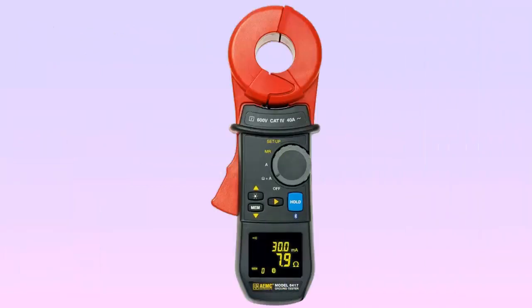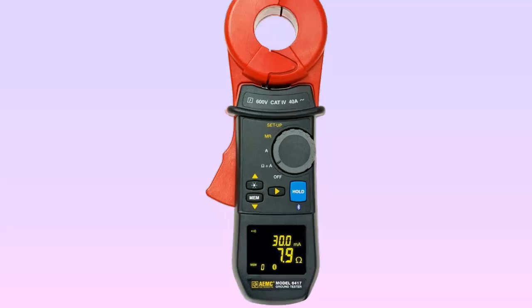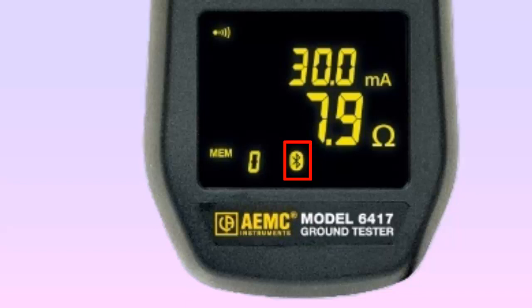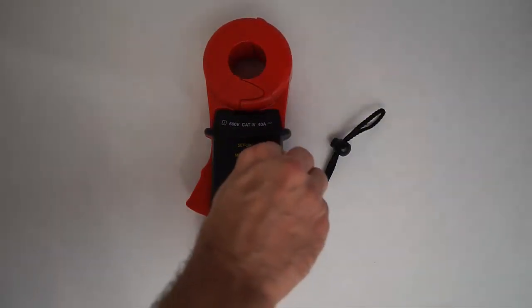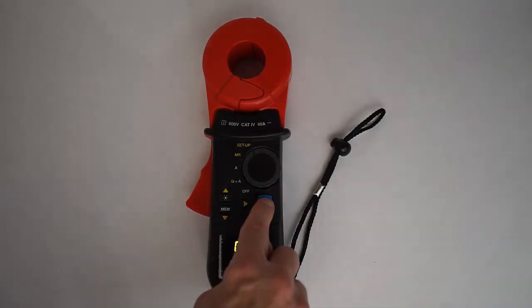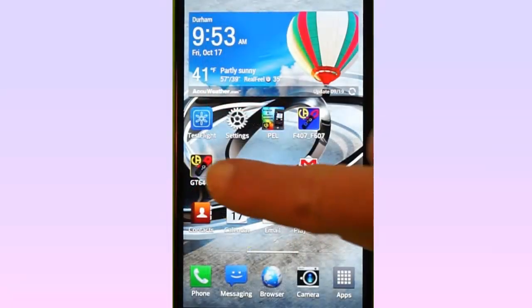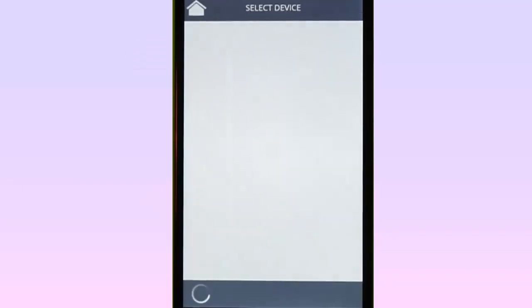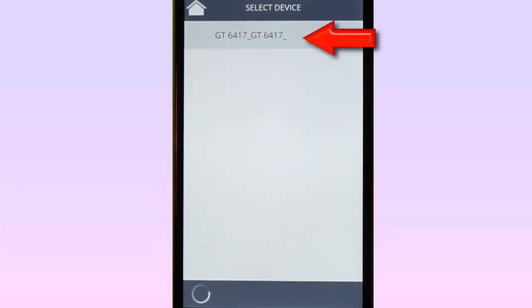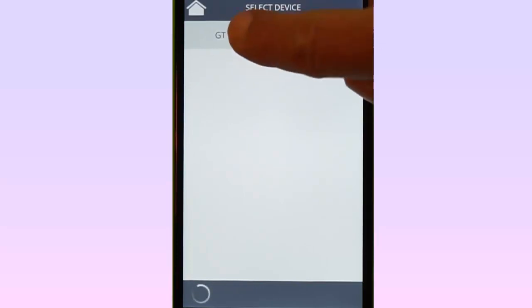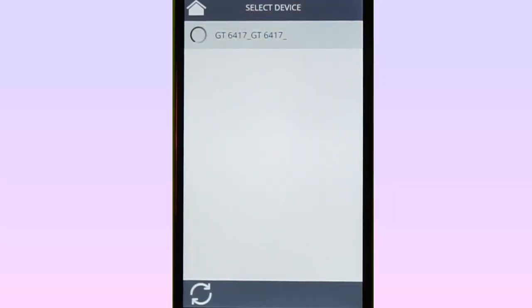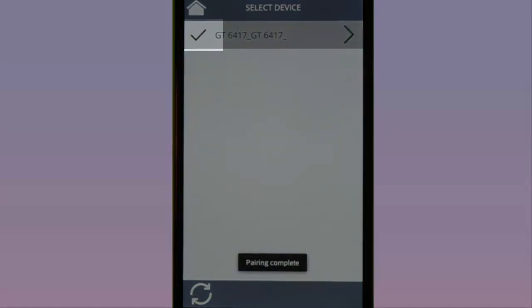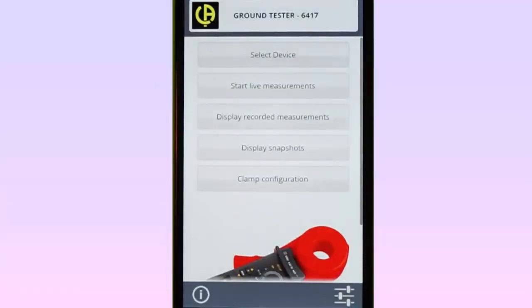To use the app to connect to a Model 6417, Bluetooth must be enabled on the instrument. With the instrument turned on, check whether the Bluetooth icon is displayed. If not, turn the rotary dial to Setup and press the Hold key until the Bluetooth indicator comes on. Start the app on the Android device. At the main menu, choose Select Device. Select the Model 6417 from the list. When the connection is established, a check mark appears next to the instrument's name. Tap the Return icon to return to the main menu.